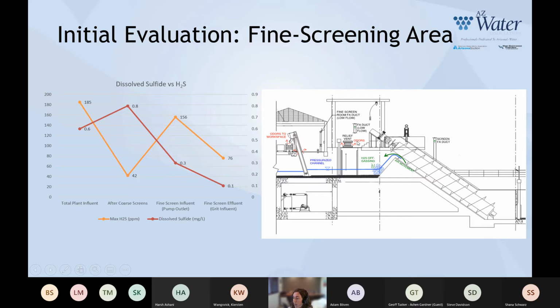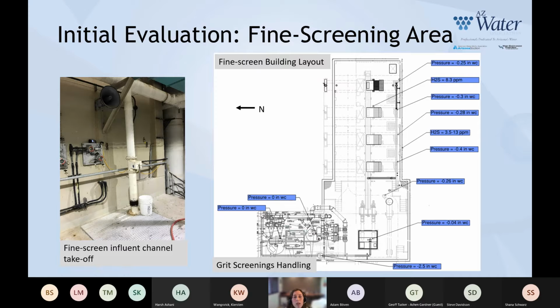And so you are seeing a lot of foul air migration at the relief vents, but also as you got to the fine screen room. The fine screen building is a single large structure with screens and a supply air ventilation located at the east end of the building. So the supply air is actually located right along the south wall of the fine screens. And that was intended to provide supply air to the entire fine screen room.